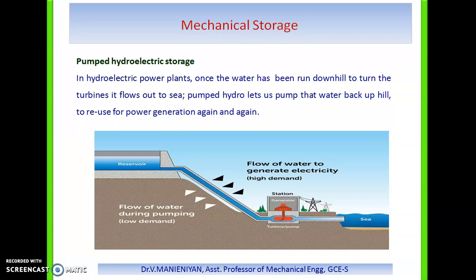First, we discuss the pumped hydroelectric storage system. Electric power in excess of intermediate demand is used to pump water from a supply at a lower level to a reservoir at a higher level. When the power demand exceeds the supply, the water is allowed to flow backward through a hydraulic turbine, which generates electric power.